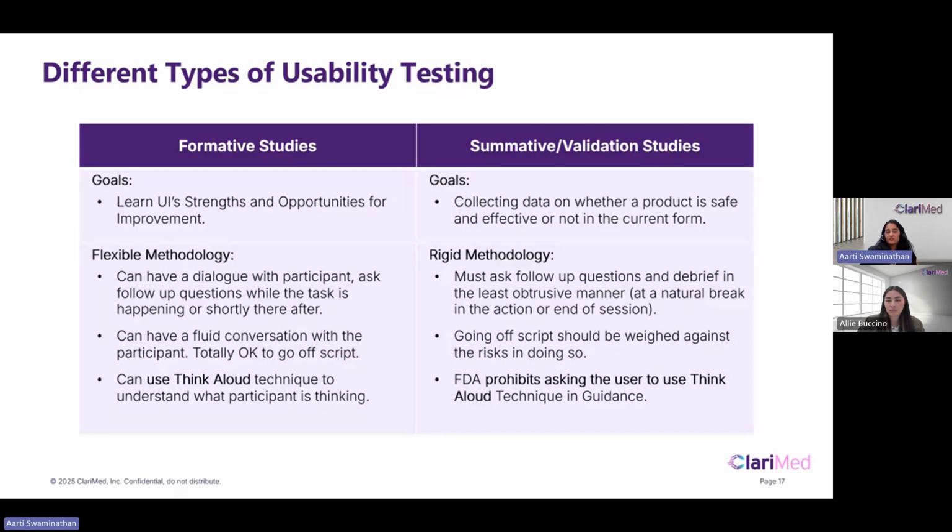So like I said, the goals are really to learn the UI's strengths and opportunities for improvement at the formative stage, versus at the validation stage, where you're really looking to prove that there are no issues, that the product is safe and effective, whether or not in the current form.